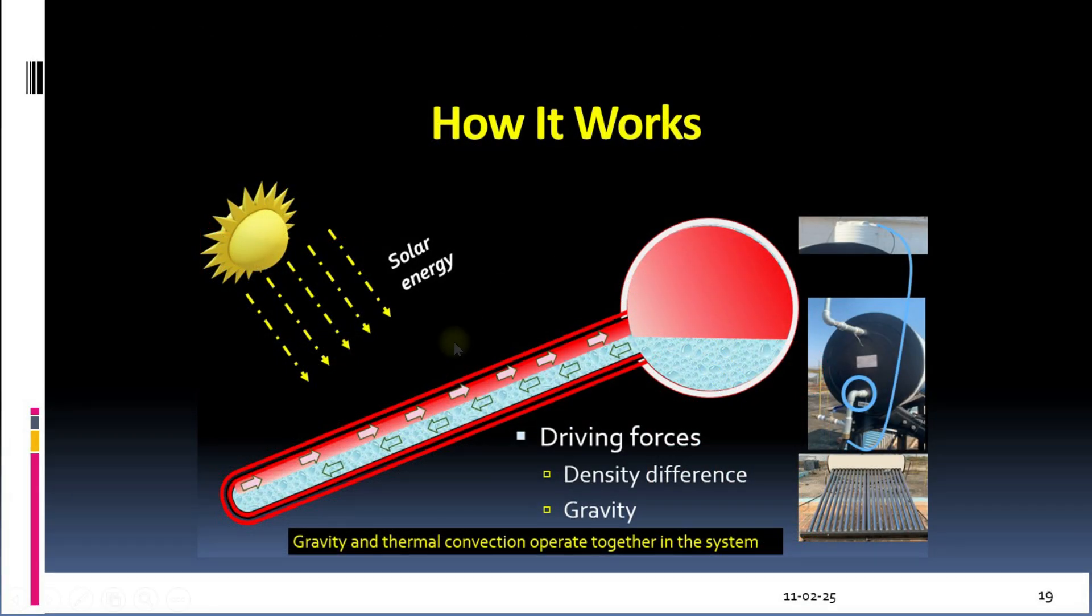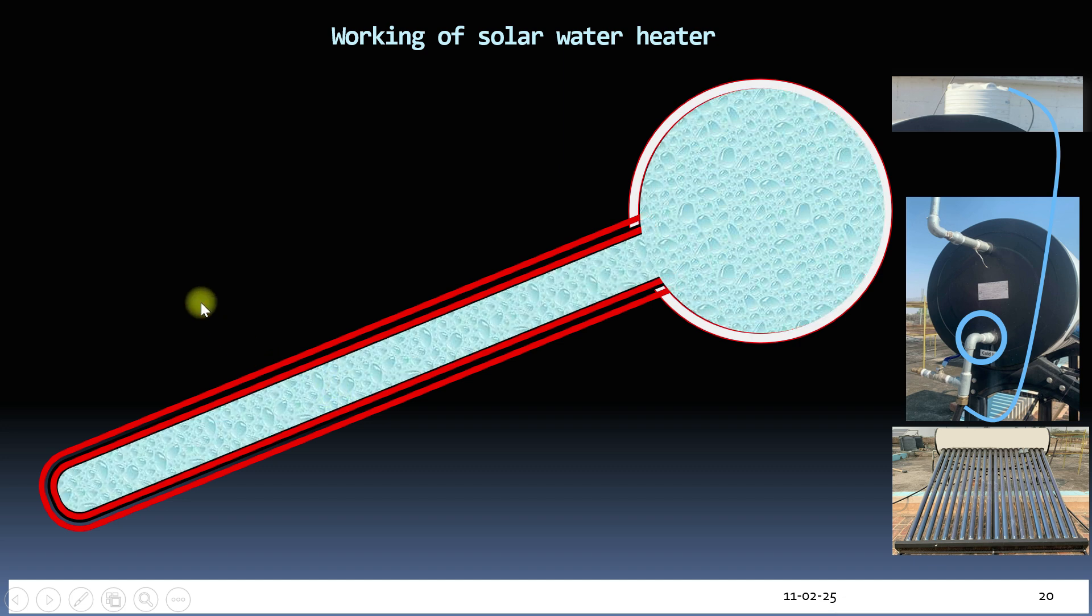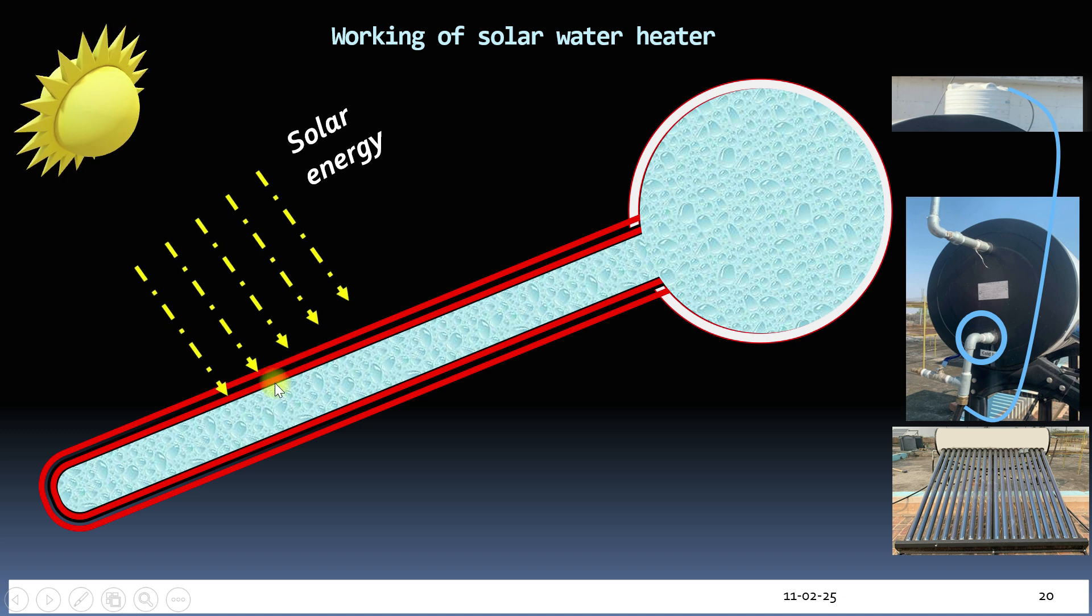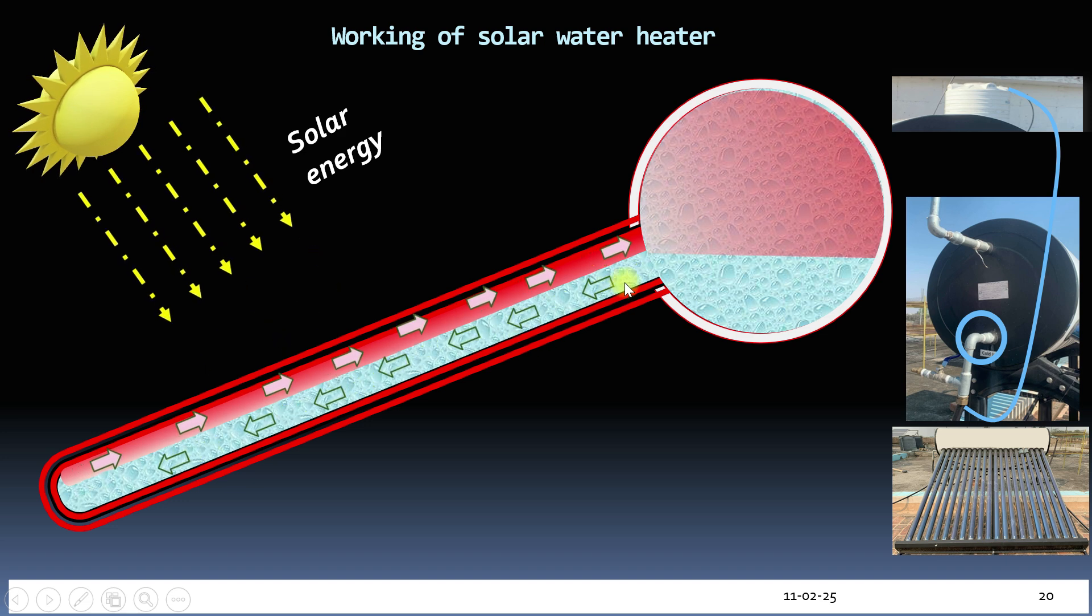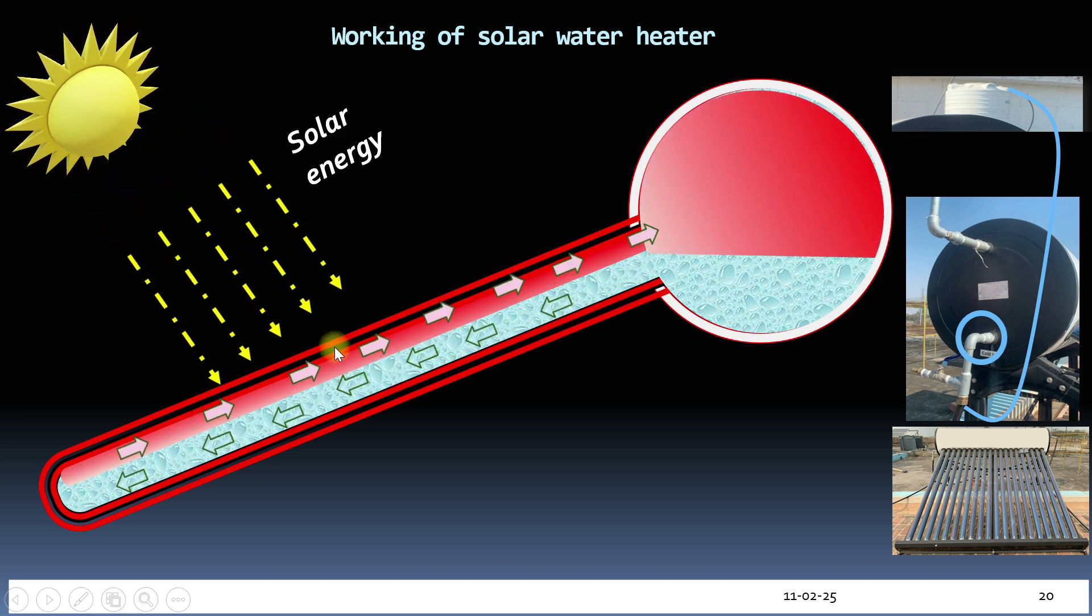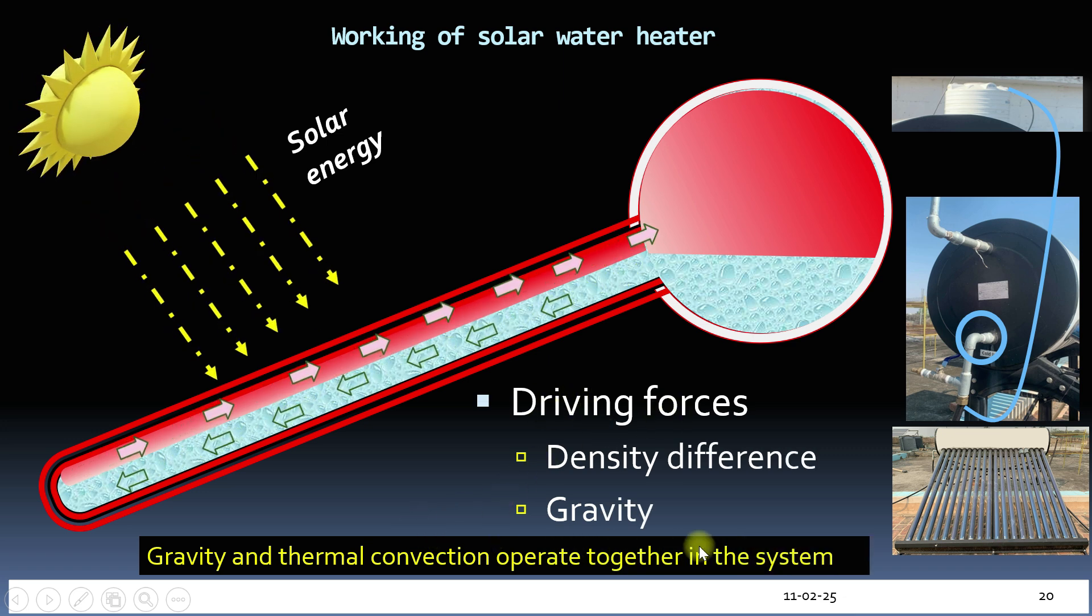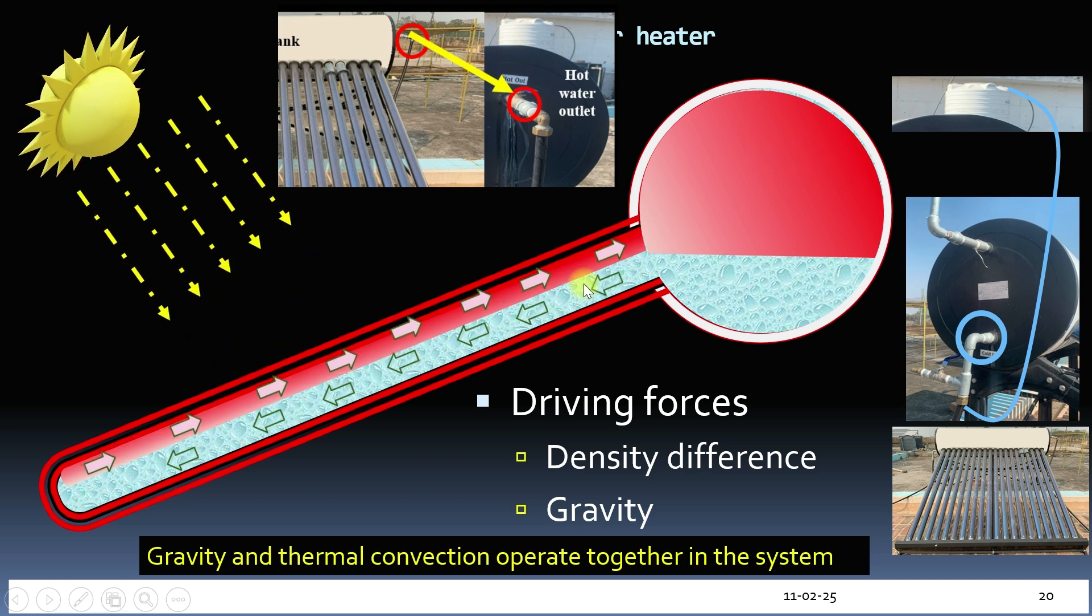Now let's see how it all comes together. Cold water is fed into the water heater from an overhead tank or with the help of a pump. When sunlight hits the evacuated tubes, the water inside heats up and its density decreases. The colder, denser water sinks to the bottom due to gravity while the hot water rises up to the top of the tank. This process is driven by both gravity and thermal convection. The hot water can be used from the top of the tank through the hot water outlet.